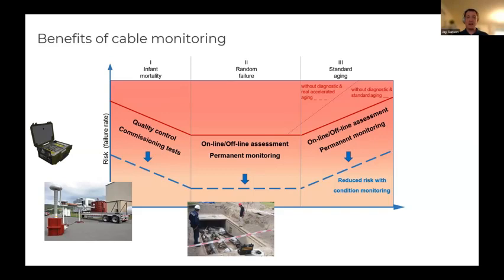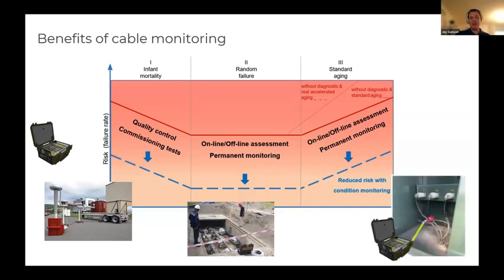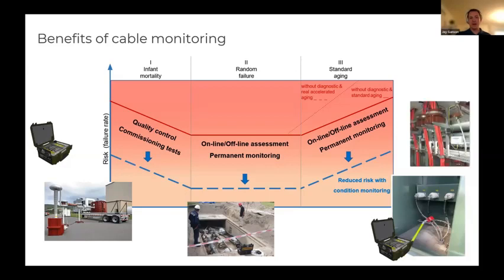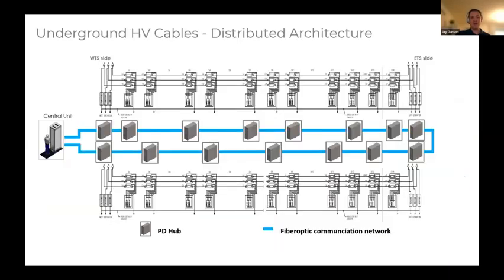When the cable itself is in life and in service, we can do PD testing. Oil-filled cable is actually really difficult to do PD testing on in the middle of the cable, which is why having oil samples in Tony's presentation is very relevant to oil-filled cables. But also, we can take that same core technology that we would use for periodic spot testing, and we can permanently install it. And this architecture that we're talking about is a permanently installed PD monitoring system for transmission buried cables. When you think about buried cables, between substation and substation or between point A and B, the cable lengths are actually smaller segments that are spliced together.